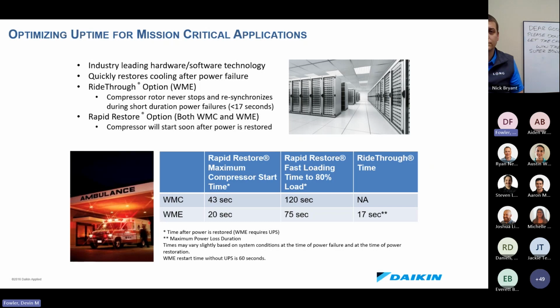If you don't have backup generators, and we do go past that 17-second ride through time, we still have the fastest loading and restart operations in the industry. Our WME chillers can restart that compressor within 20 seconds of power being restored. Then we can be up at 80% load within 75 seconds of that compressor start, leaving only 95 seconds after power is restored until you're back up and running with a sustainable load on your building. Like I said, we are the fastest in the industry at this time, and we are the only ones in the industry that offer ride through.